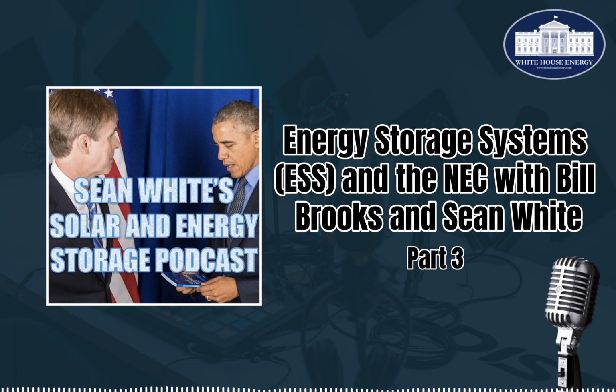sense? Power supply can have less capacity than the calculated load. So we don't need to be able to supply the whole calculated load. And the power supply shall be at least as much as the largest load. And some people used to take this as like, oh, the inverter has to be at least as much as the largest load. But it could also be a generator or a generator plus an inverter. All you have to do is be as big as your largest load. So it's possible that somebody could have a huge load that's bigger than what their solar inverter can handle, but it only works when the generator is turned on.